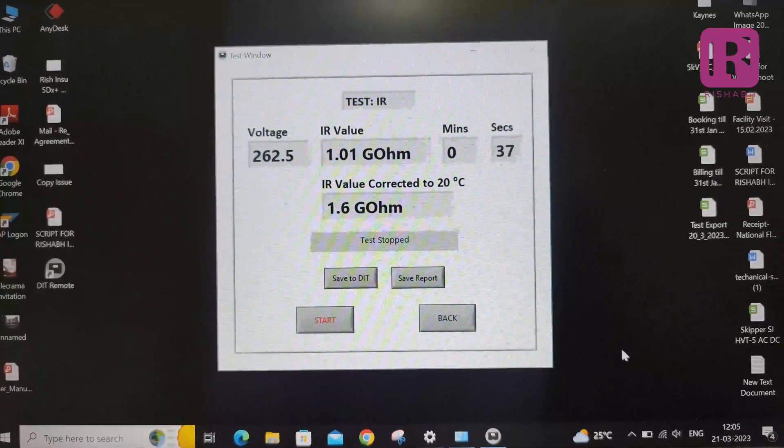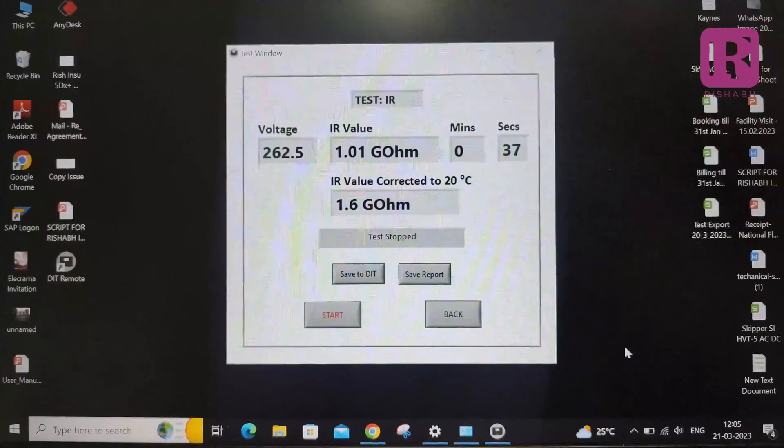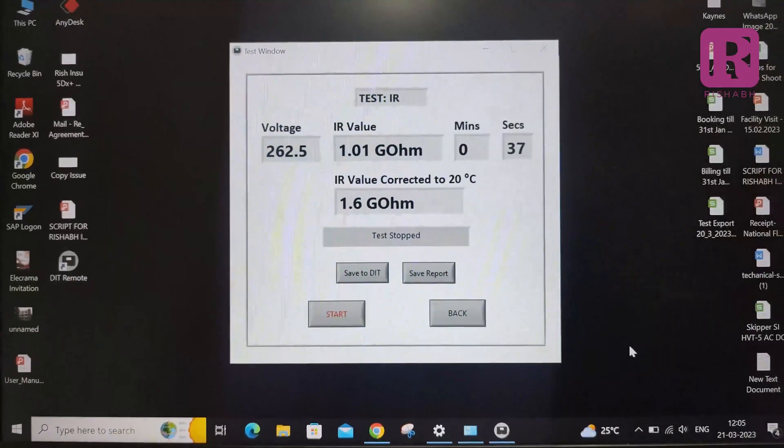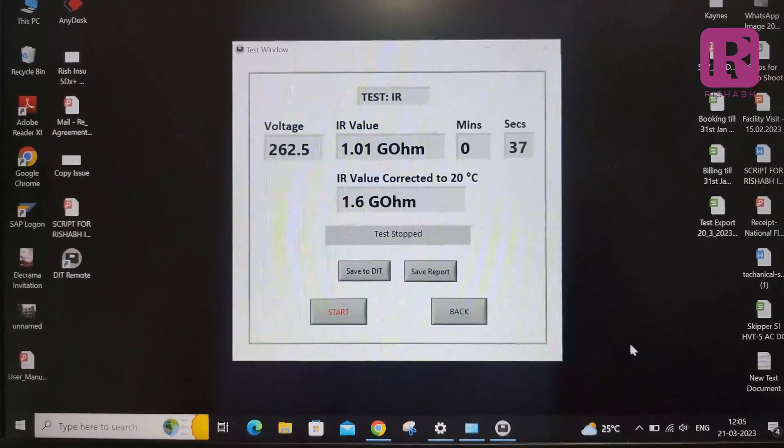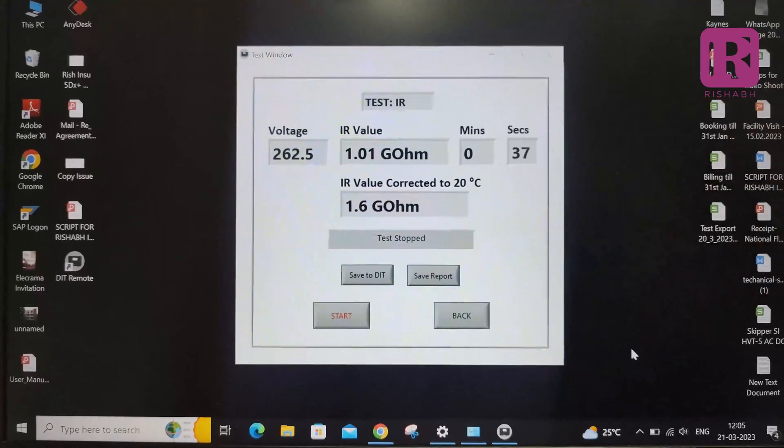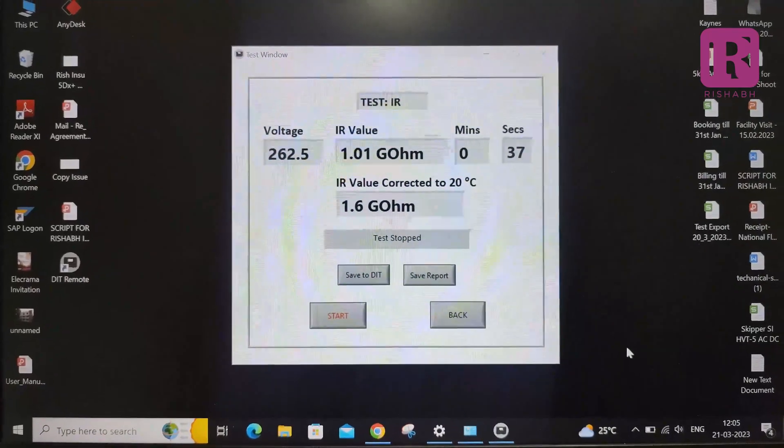The IR value of 1 Giga Ohm is calculated at ambient temperature 30 degree Celsius and the corrected value of 1.6 Giga Ohm is calculated at 20 degree Celsius automatically.